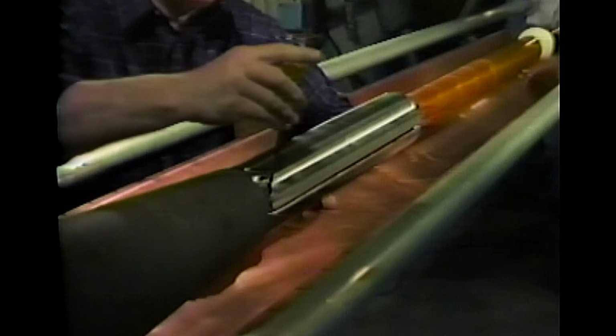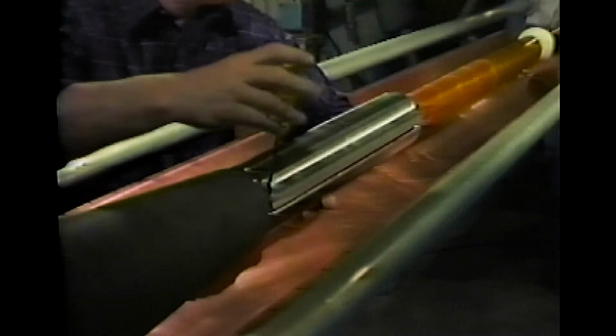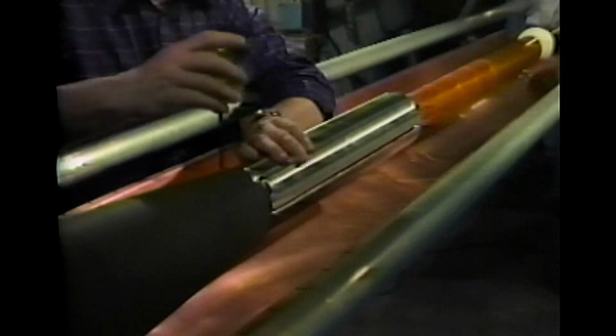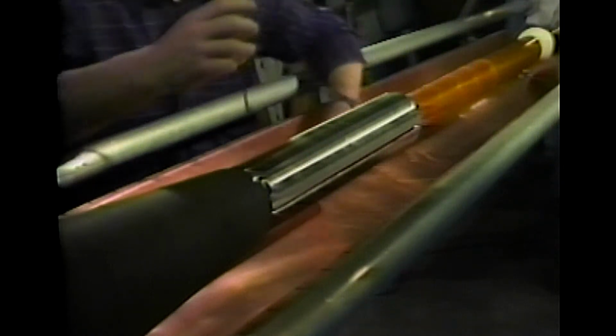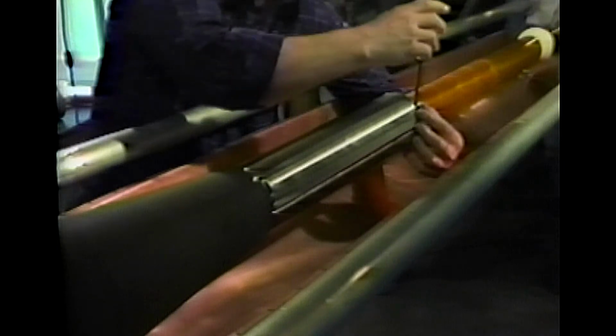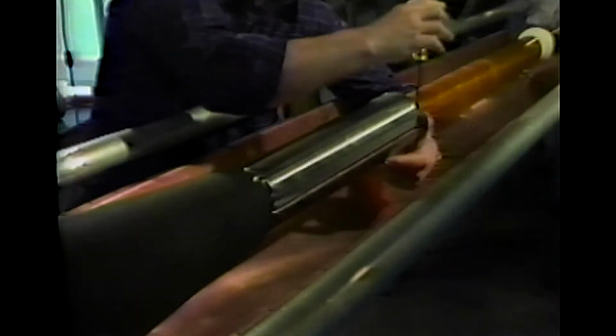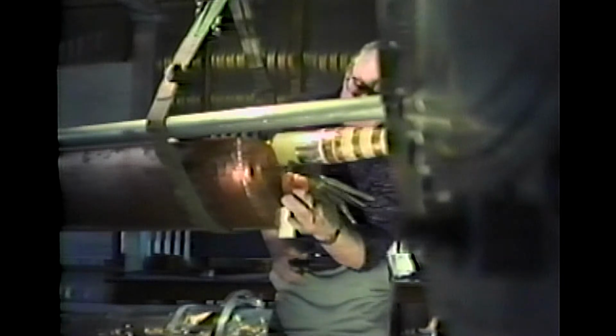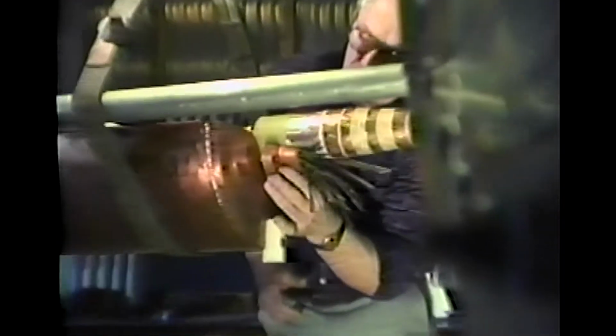The component of the termination which actually crosses the temperature transition region is known as the cryogenic bushing, and here the connection is being completed between the bushing and the inner conductor of the superconducting cable. Small adapting pieces are fitted to connect the conductors of the termination to the prepared ends of superconducting cables.